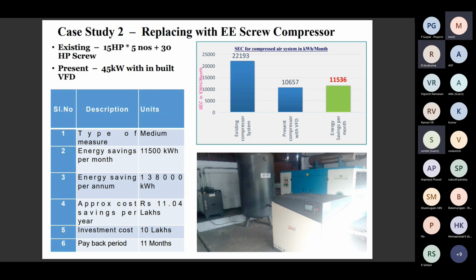Another example, one more foundry. They have one small screw compressor and the rest are reciprocating only. So all the existing compressors were replaced with one single compressor. So they are able to save nearly 1,38,000 units per year, and the cost saving is 11.04 lakhs only. All put together, compressor, receiver and the air dryer, the investment cost is somewhere around 10 lakhs, so the payback period is only 11 months.